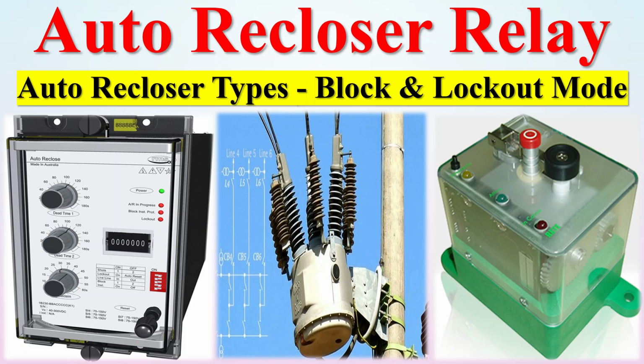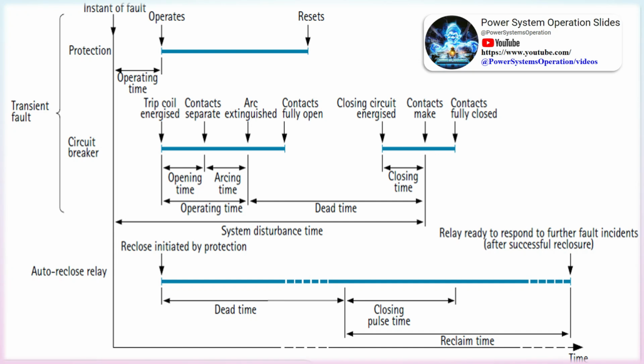Ensuring continuous power flow through transmission lines is crucial, and interruptions should be minimized. Faults on overhead lines can be either transient or permanent. Transient faults often clear themselves without intervention, allowing the relay auto-recloser to close the breaker after it has opened due to the fault. Fault types: transient faults.